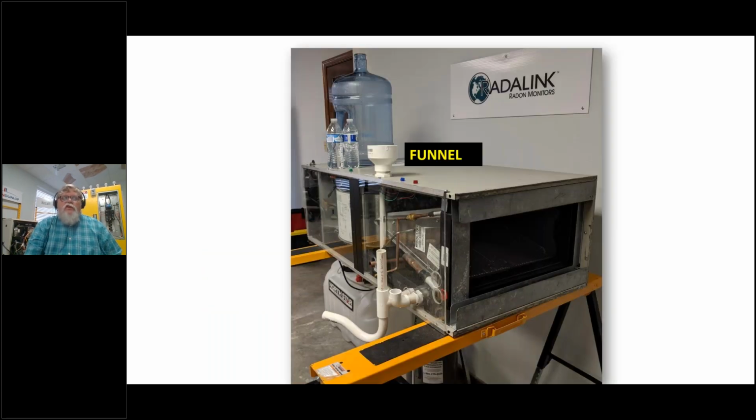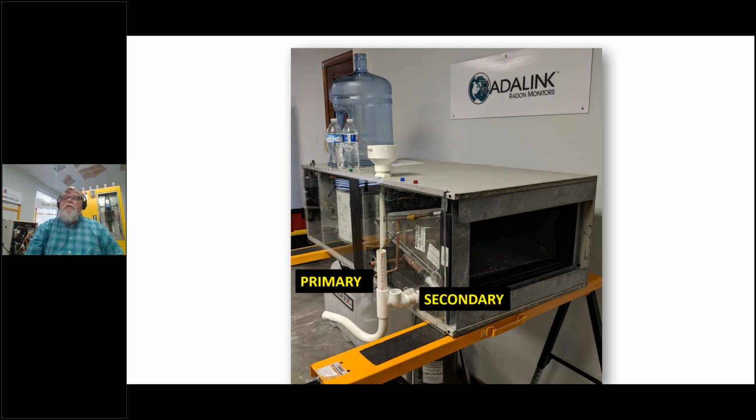If you look at this unit here we have right in the classroom, there's my funnel. What we do is we pour water in this, we flood the pan, and if you look at the way this unit is set up, there's your primary drain. Here's your secondary. I see this installation all the time. People will put a pipe and maybe an elbow and turn it up on the secondary, and on the primary they'll put the trap in there, but then they'll put a clean out pipe or a vent pipe in the opening and they'll leave it open.